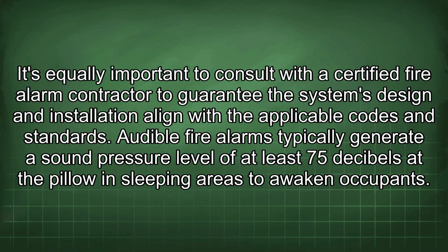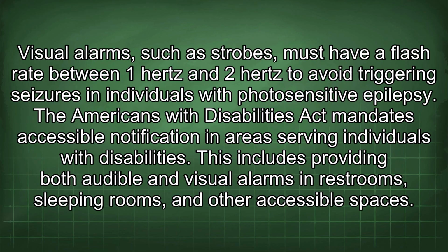Audible fire alarms typically generate a sound pressure level of at least 75 decibels at the pillow in sleeping areas to awaken occupants. Visual alarms, such as strobes, must have a flash rate between 1 Hz and 2 Hz to avoid triggering seizures in individuals with photosensitive epilepsy. The Americans with Disabilities Act mandates accessible notification in areas serving individuals with disabilities. This includes providing both audible and visual alarms in restrooms, sleeping rooms, and other accessible spaces.